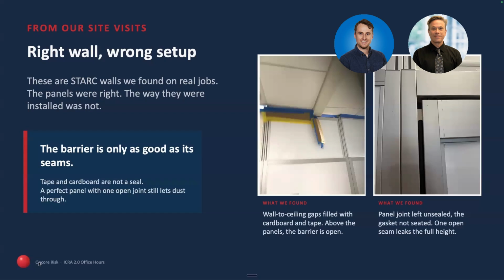Yeah, you make some good points, and I'm sure the reason your company develops some of these products is they're easier to put up, but they still have to be put up correctly. You have some challenges going around elevation issues of the ceiling, and in this case, in the middle, the elevation came down about 3 or 4 inches, and they didn't use the adapter. They could have done it wrong with a plastic barrier or any other barriers as well. So those are great points.